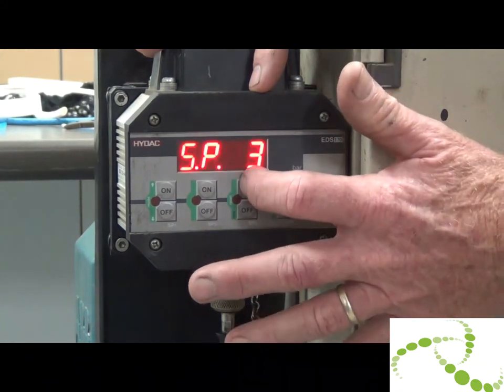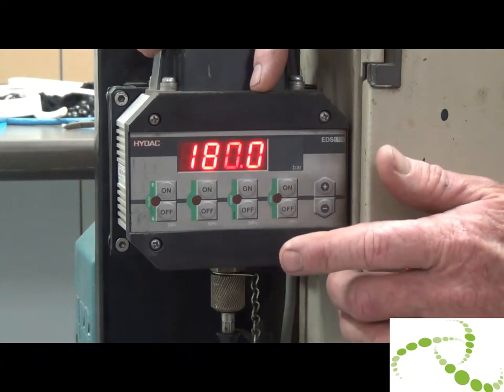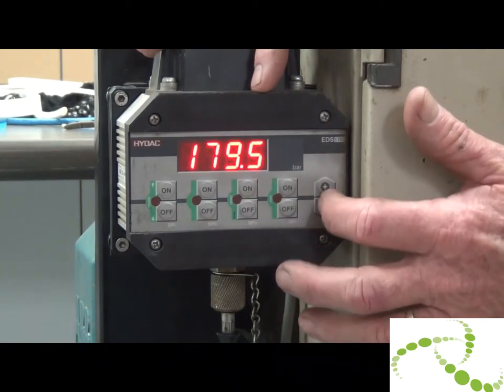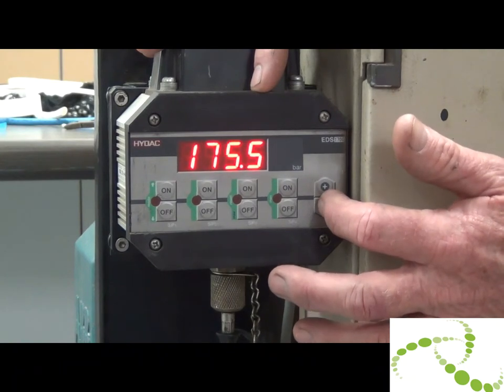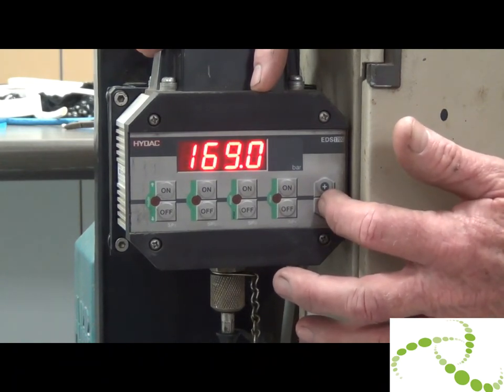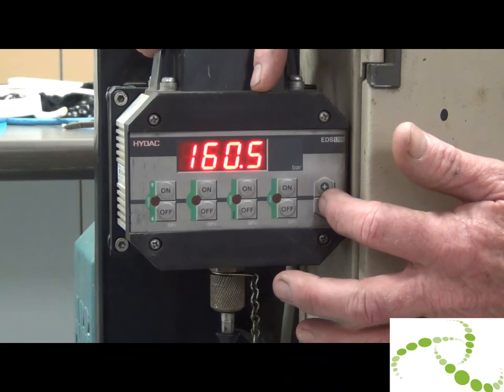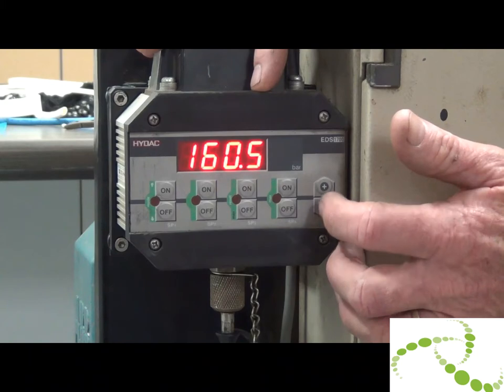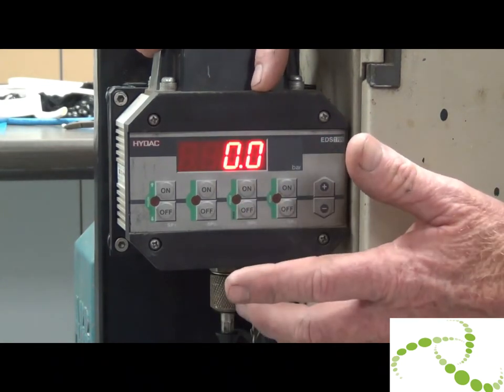The third one is your retract for both rivet setter number one and rivet setter number two. Now normally this is set to about 160 bar, which is more than good enough generally, but you can increase it if you are having problems. Wind that down using the minus, and if you want to increase it, use the plus arrow up. Then you press the F key. That sets it.